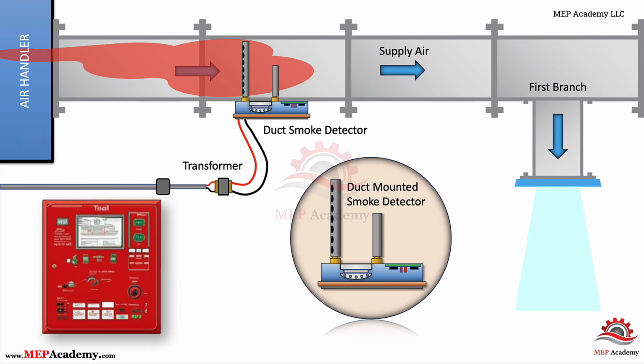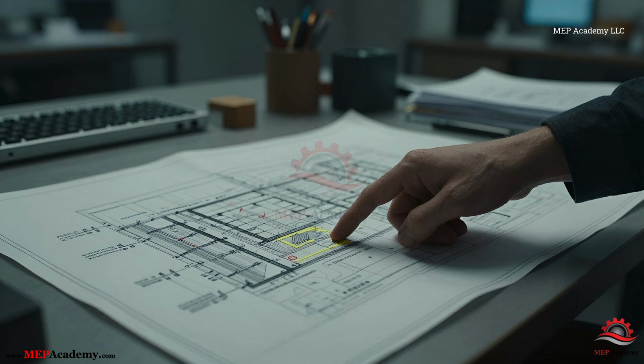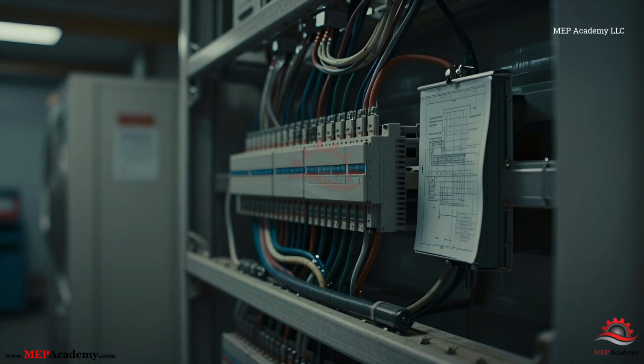The problem often appears during final inspection when the detector is installed, but the shutdown sequence does not function correctly. Building codes require that air-moving systems shut down upon detection of smoke to prevent distribution through duct systems. While the exact implementation varies by jurisdiction, requirements commonly reference the International Mechanical Code and NFPA 90A for air distribution systems. The key coordination issue is not the code requirement itself, but ensuring that power, monitoring, and shutdown wiring responsibilities are clearly assigned before installation.